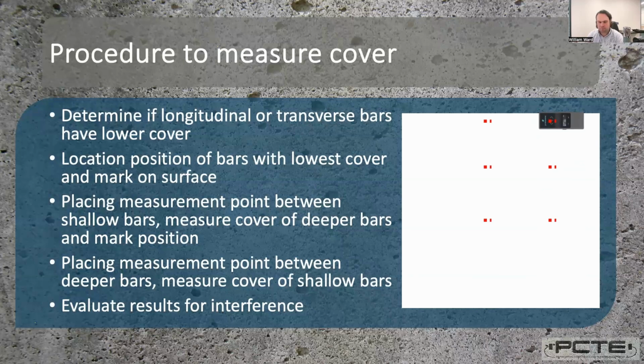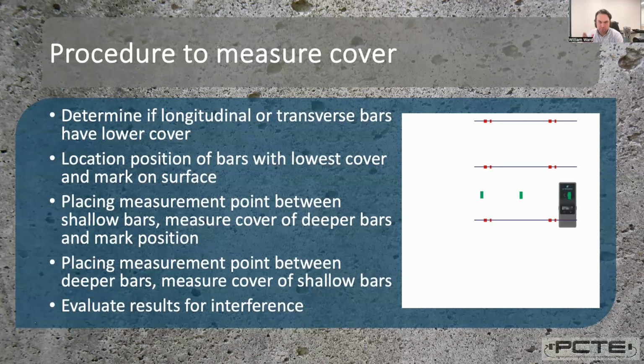And the first bars we cross, there's two things we don't know about them. We don't know if we are moving the probe on top of a bar that is parallel to its path of travel. And we also don't know if we are on the bars closest to the surface or the reinforcing bars that are sitting in contact and beneath the bars closest to the surface. So we're going to discard anything but the position on the first passes of our cover meter. On the second pass, we can take the measurement point of our cover meter. Again, that is lined up with the LED indicators on the PM8000, and we're going to pass that in between the parallel reinforcing bars.